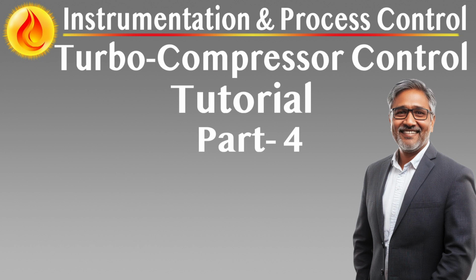Location and accessibility. Field transmitters and switches are mounted outside hot compartments where feasible. Devices are positioned for easy access during operation and maintenance. Vibration probes and thermocouples are installed on rotating and static parts per OEM recommendations. Instrumentation for performance testing. The vendor shall provide dedicated taps and fittings to support live performance testing, additional instrumentation to capture turbine output, compressor efficiency, and stage-wise pressure ratios.